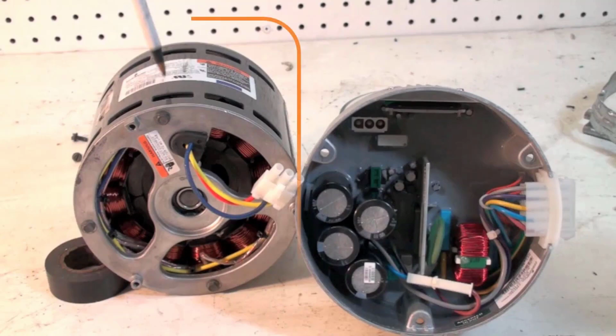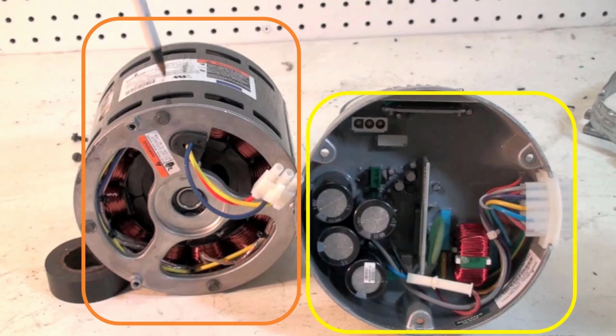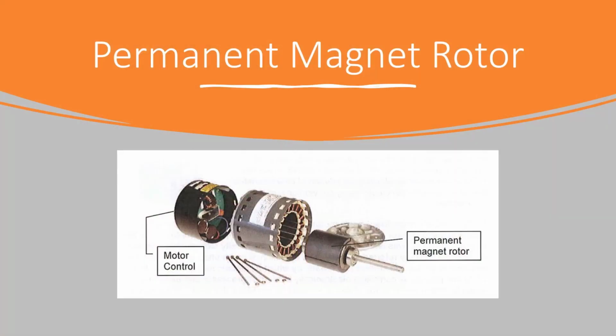The ECM motor consists of the main motor body and then the electronic module that attaches to the end of the motor. This controls the torque, RPM, and CFM that the motor is being commanded to run at. The ECM motor is a pretty bulletproof motor. The electronic module is sealed so it's not susceptible to moisture that may get on the motor. And the main component of the ECM motor is the permanent magnet rotor, which is a pretty heavy, durable rotor. And we've had very few motor failures on these ECMs.